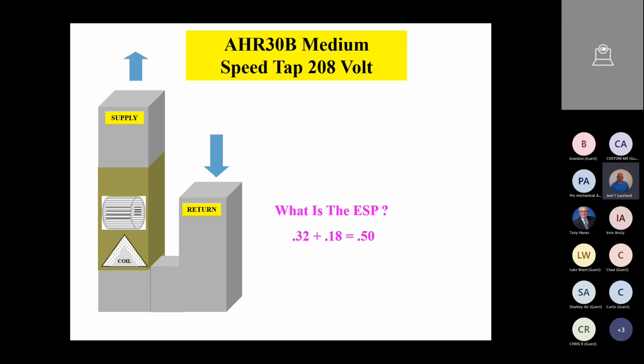So referring to the chart, what is the CFM? So again, an AHR 30B medium speed tap on the 208 portion of the chart, 0.5 inches of static. What is the CFM? Does anybody have that? Put it in the chat or unmute your mic and tell me what the CFM would be under those conditions. Okay, if you're reading the chart properly, it should read 890 CFM. There you go.